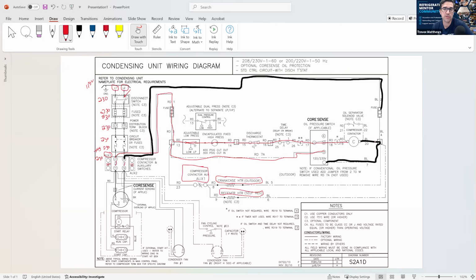You put it on 2, you should have 230. Put it on 3, you should have 230. Put it on 4, you should have 230. And put it on 5, terminal block 5, you should have 230 because the contactor coil is a load. And we got 115 on this side, we got 115 on this side, which equals 230 when you energize it. And that's what's going to energize that, have that magnetic field, which will pull in the contacts.